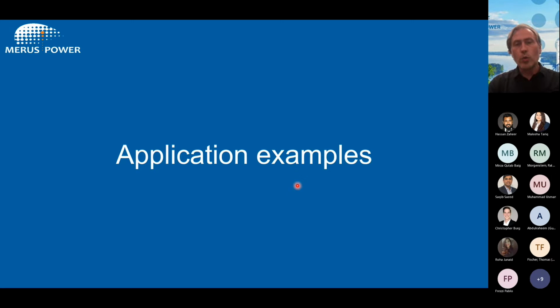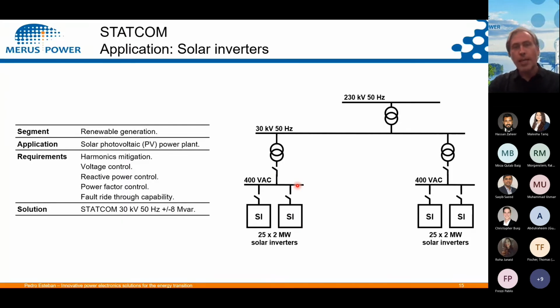If we are having a look at some application examples, the first application here will be solar power plants. And one of the main problems that we have in solar power plants are solar inverters. Anyways, this is a very general diagram. Solar power plants can be built in many different ways, but the idea is that you have inverters there, and the inverters are connected together. You can have step-up transformers to connect to the substation voltage, 20 kV, 30 kV normally.